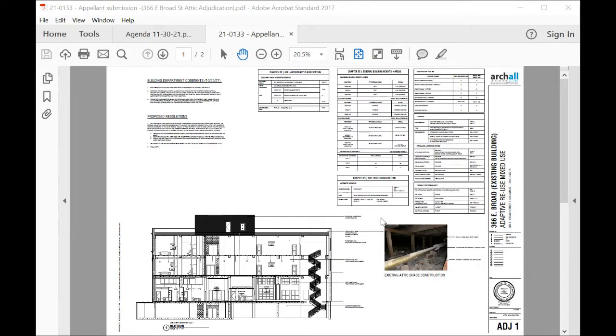So we're here today with a full 13 system throughout the building. It would require that sprinkler systems be installed in this cavity space. The intention for the project was to not replace the existing roof membrane, as it was a fairly new roof to this building, as well as relocate additional equipment to gain access to install the fire system within the cavity. We would also have to heat that cavity, unless we did a dry system for just that small area.